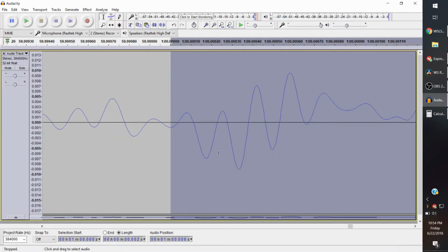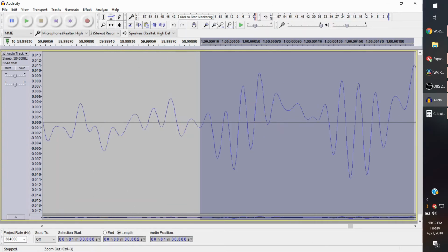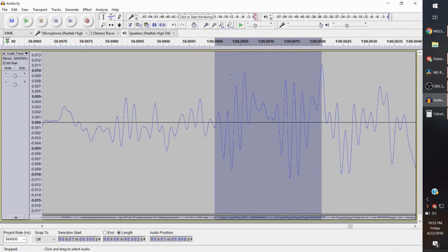But how can you tell if you're running slow or fast? Well, that's easy. If I zoom back out here in my program, you can see my 60-second peak was over here, which is after the 60-second mark. That means my beat was slow compared to the atomic clock, and if I'm slow, that means I'm running behind. So my accuracy is 2.88 seconds slow per day.